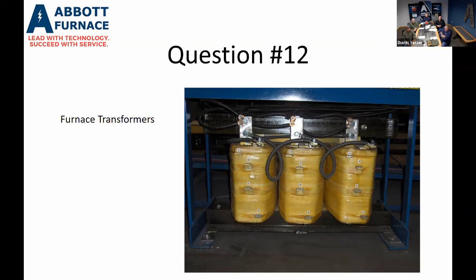So you have to determine, if you look at your SCRs, the SCRs also have what they call a current limit on it. And that's going to limit the current that's going out to this transformer to protect it from overheating. If you would happen to take that too high of a tap and reach that max current, and the max current is going to be determined by your transformer size. So the example is, if you have a 60 kVA transformer, you want to take 60,000 divided by the voltage that you're supplying to that transformer, which is typically 480 in North America. And then you divide that by the square root of 3, which is 1.732. And that'll tell you what your amp.